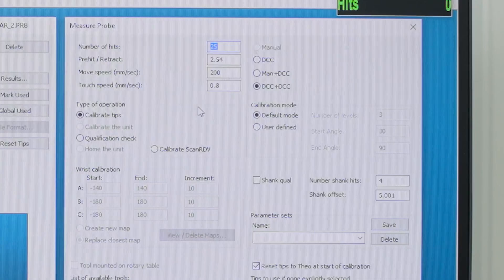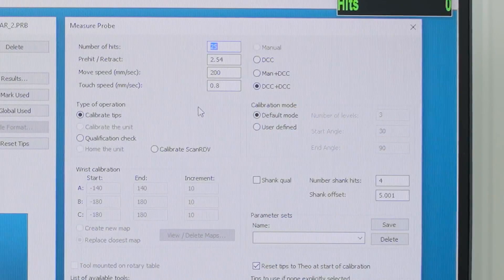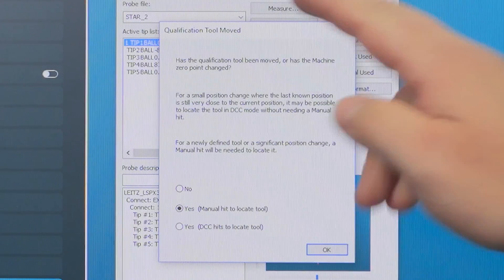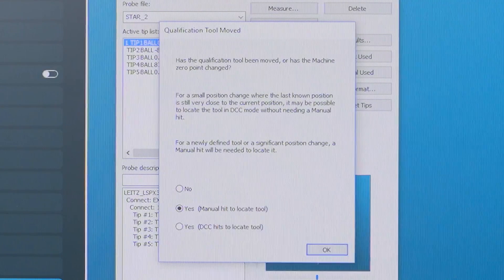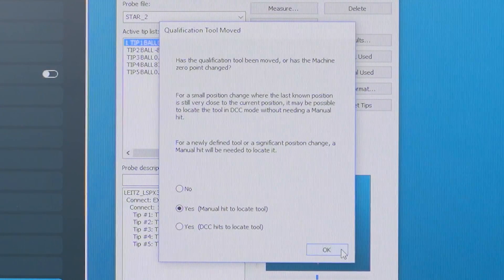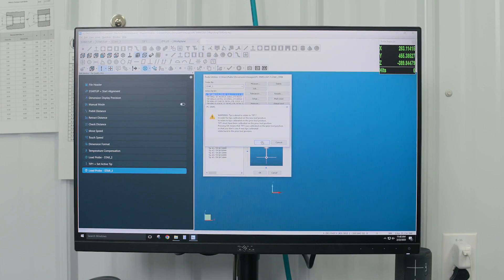Click measure. We'll be on DCC mode. We're going to click measure. This asks if our qualifying sphere has been moved. Yes, it has moved, and I'm going to do a manual hit today. Now we're going to go to the CMM and we'll tell it where that sphere is at.